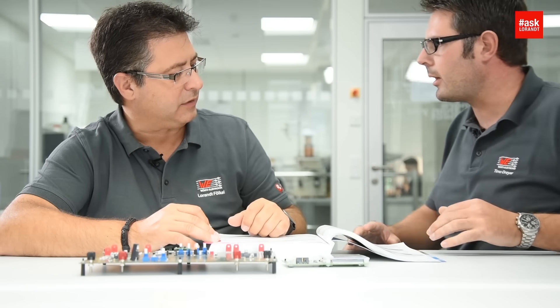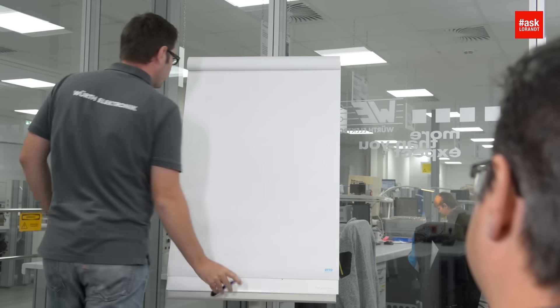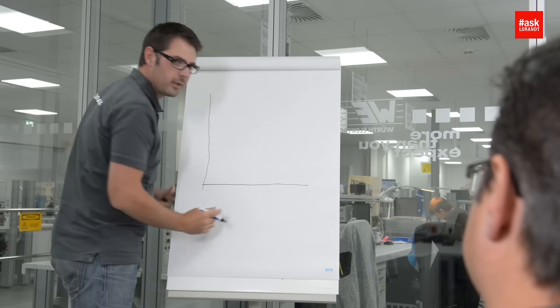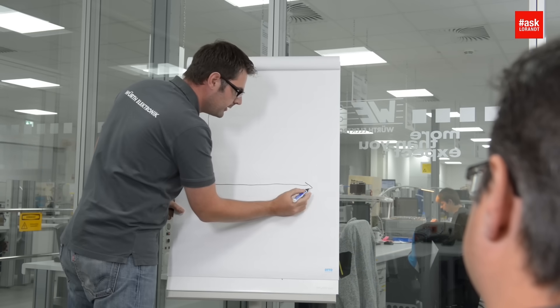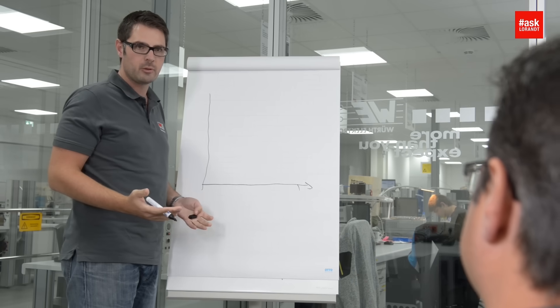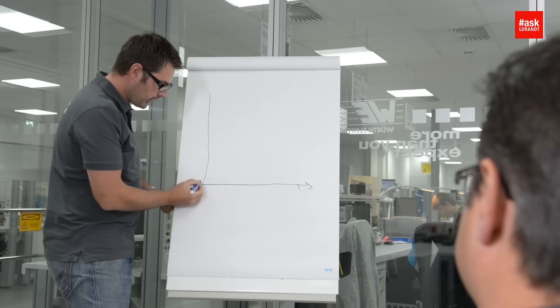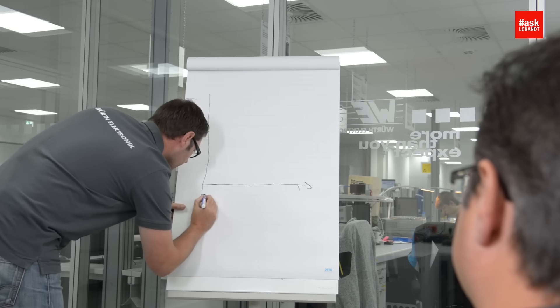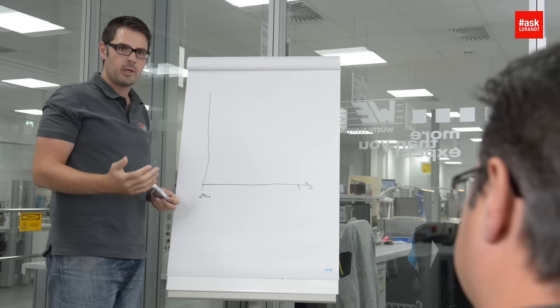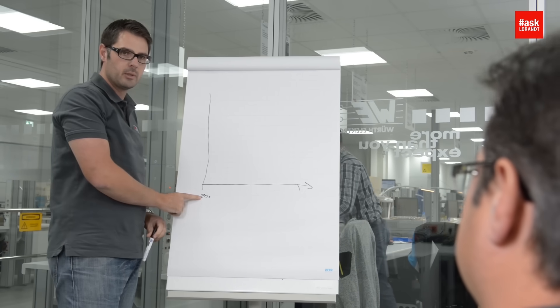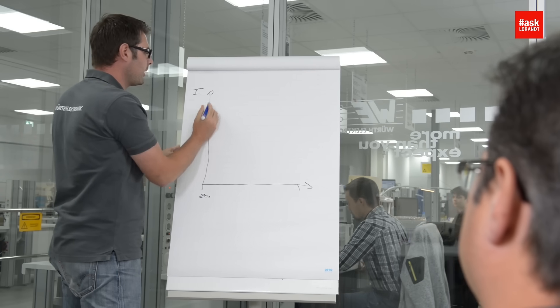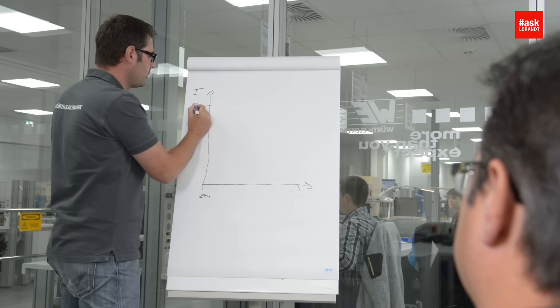Yes, of course. Let me take the flip chart. So Laurent, when we speak about derating, first we have the Y-axis and the X-axis. On the X-axis we have our maximum temperature — in this case, for that connector, 105 degrees maximum. Where the axes cross each other, we have 20 degrees, because we measure the maximum current under lab conditions, which means 20 degrees. Then when you look in the datasheet, we have the 3 amp maximum current — so here we write down: 3 amp.